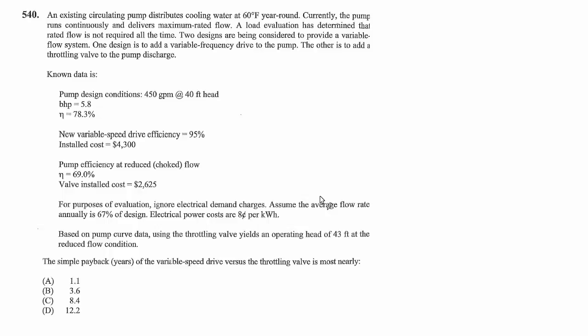Known data is pump design conditions: 450 GPM at 40 feet head, brake horsepower 5.8, and efficiency 78.3%. New variable speed drive efficiency is 95%, and installed cost is $4,300.